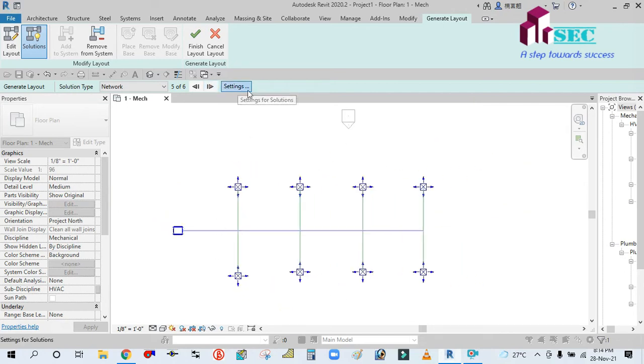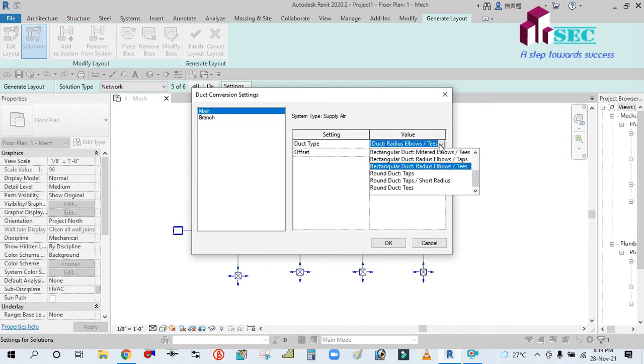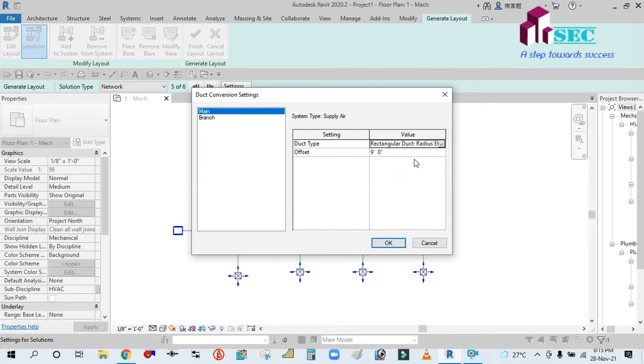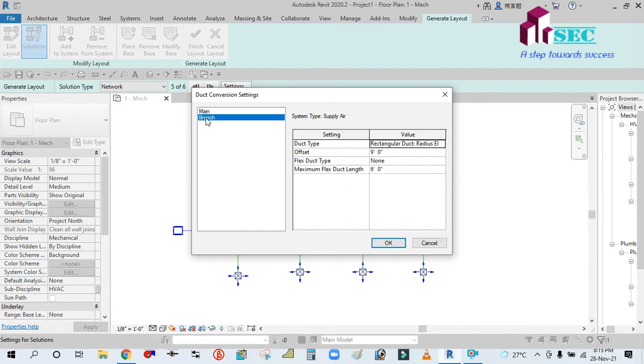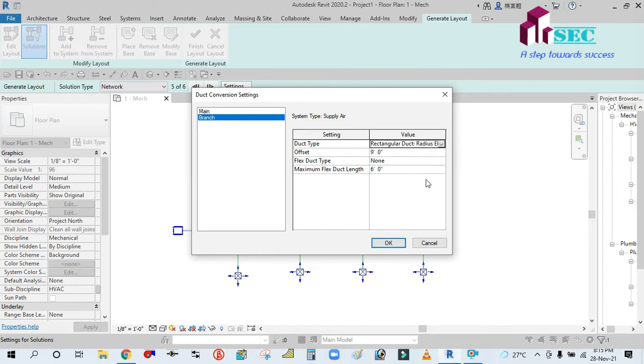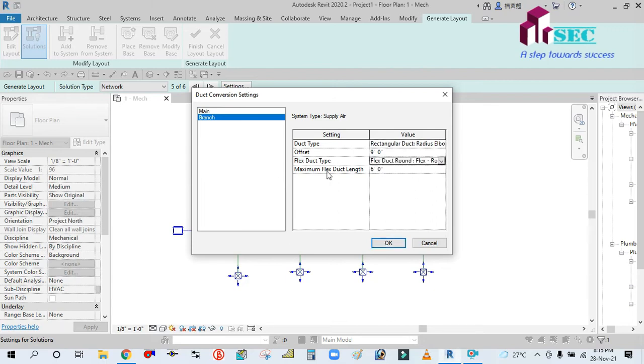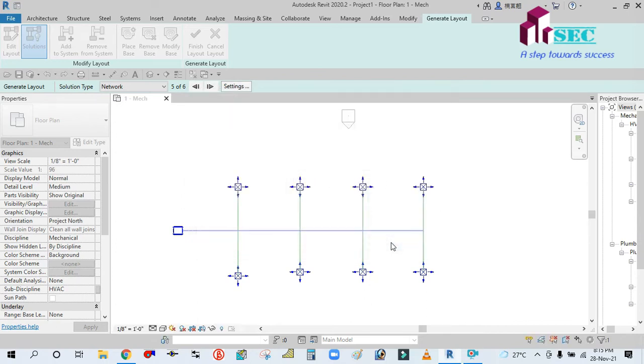Select it and then go to setting. The main duct is at 9 feet. Select the duct type, rectangular duct, duct radius elbow type, branch type is rectangular elbow, offset is 9 feet, offset of branch duct in 9 feet. Then flexible duct, flex duct round, then flex duct length is 6 feet. Then okay, okay, after finish.